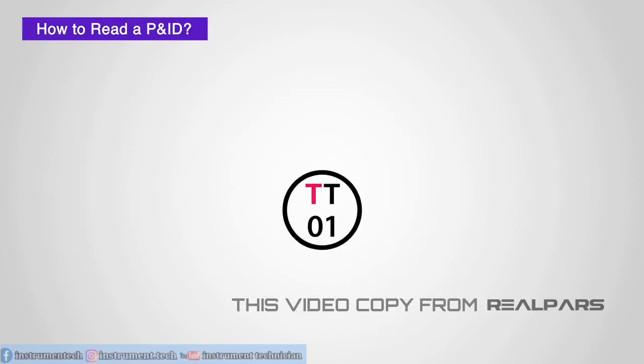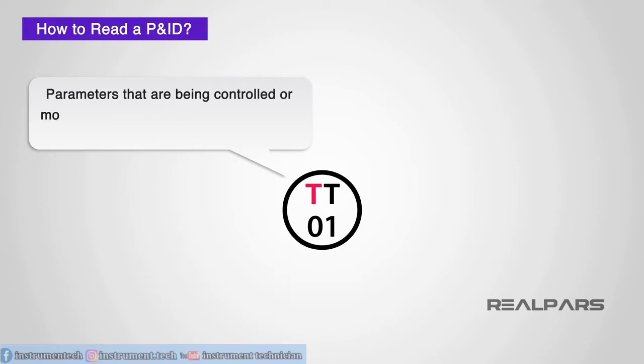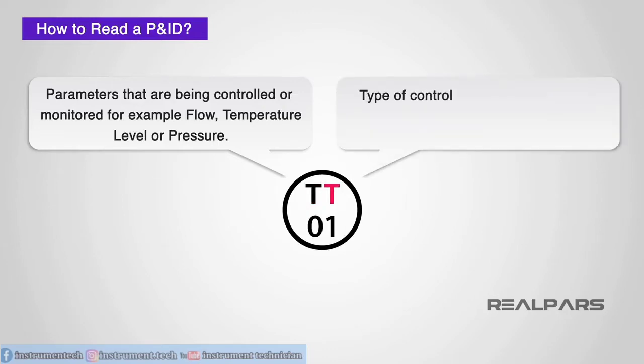The first letter of the code identifies the parameters that are being controlled or monitored, for example: flow, temperature, level, or pressure. The next letter is used to define the type of control device being used, for example: transmitter, valve, or controller.